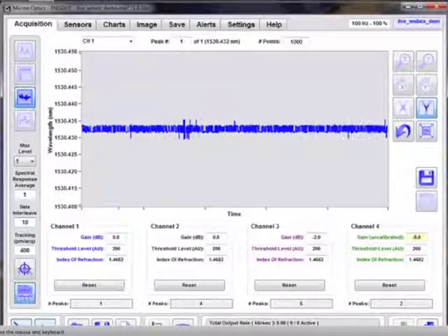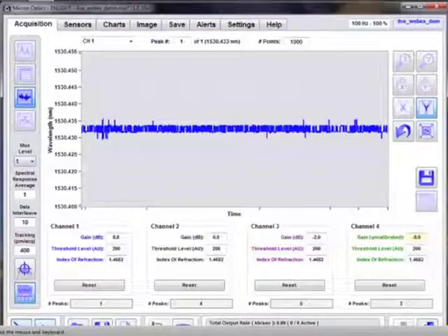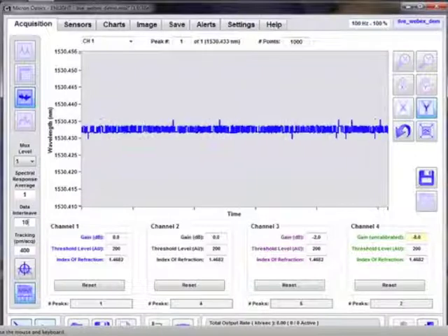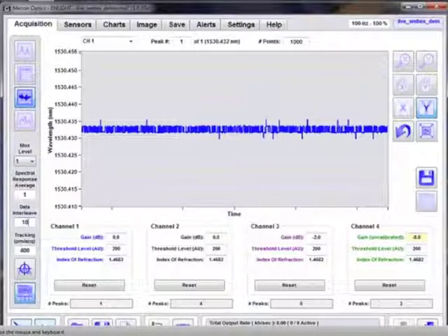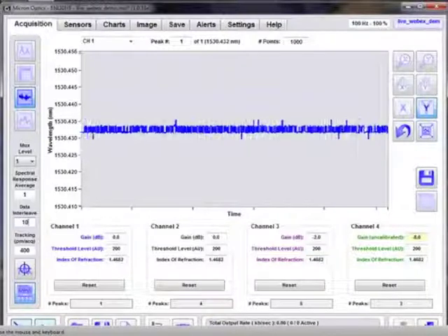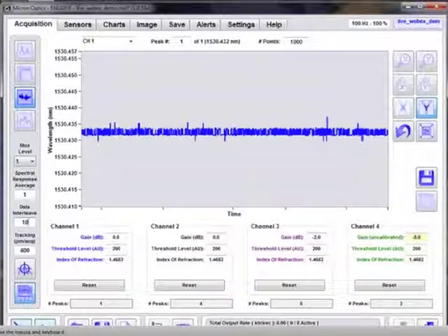so you can still set an averaging of 10,000, say on a 4-channel system, and set the data interleave to be 10 or 100 or even 1,000. So now you're receiving data once a second, but you're still gaining the advantage of averaging it using 10,000 data points. So over an extremely slow cellular network, you're able to still receive data, stream data, make sure you don't miss any data, but again, have all the benefits of averaging over 10 seconds without the need for the bandwidth to transmit all that data to your system.